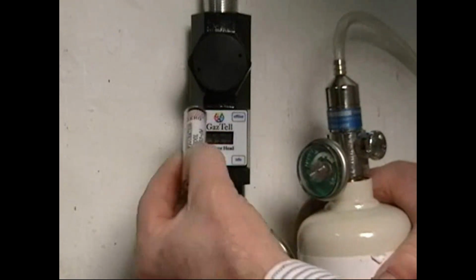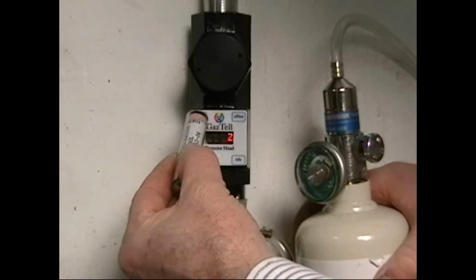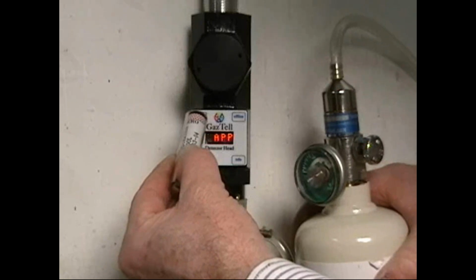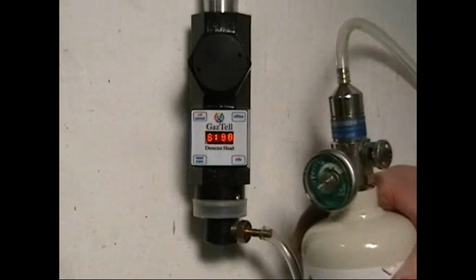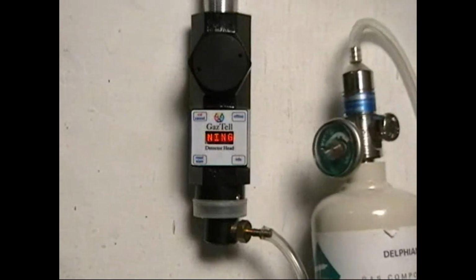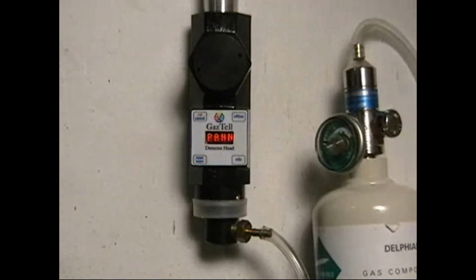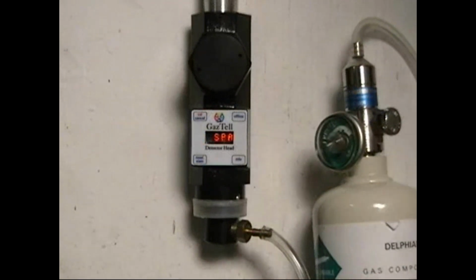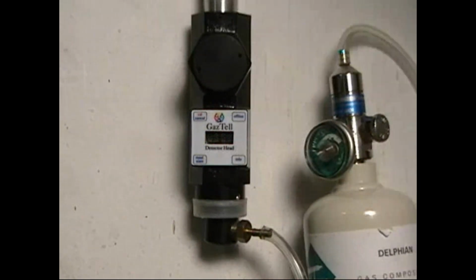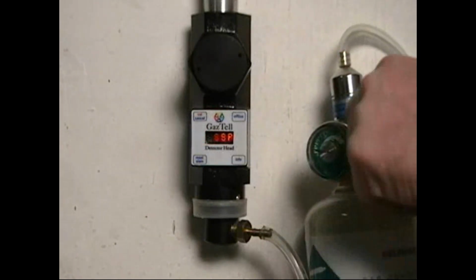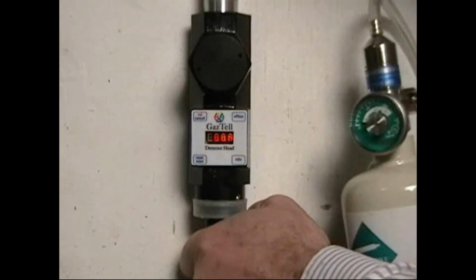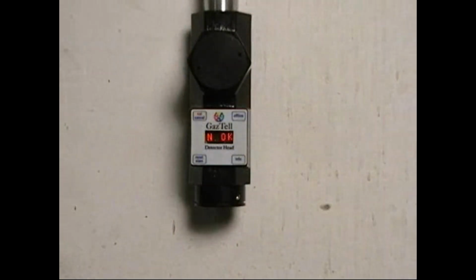To start span calibration, connect your span gas to the calibration cup and turn on the gas regulator valve. Hold the red end of the calibrator over the cal mark for 5 seconds. The display will scroll apply span gas or spanning if the sensor recognizes that the gas is being applied. The spanning sequence typically takes about 30 to 40 seconds. After a successful span calibration, span OK, remove span gas will be displayed. Turn off the regulator valve and remove the calibration cup. The gas will slowly dissipate from the sensor chamber, but this can be sped up by applying zero air to purge the gas.